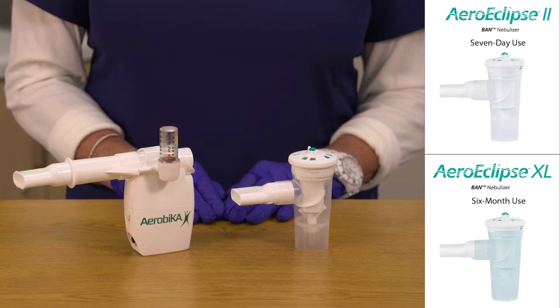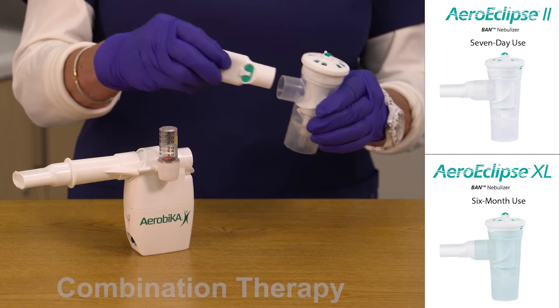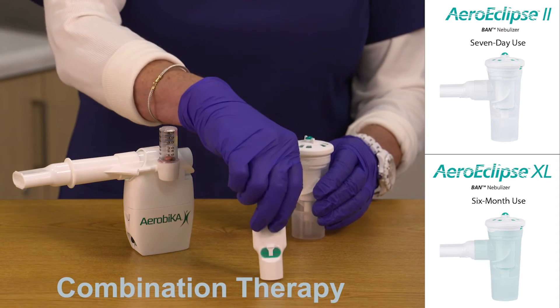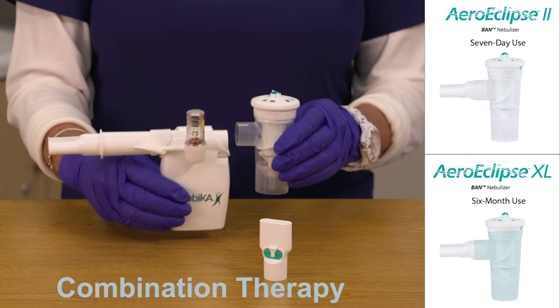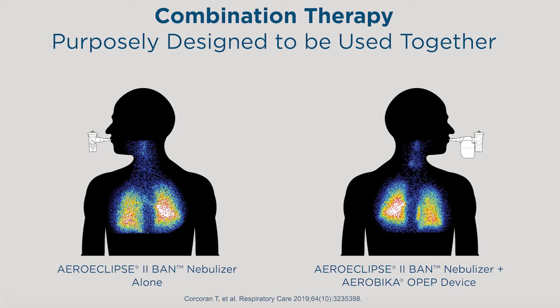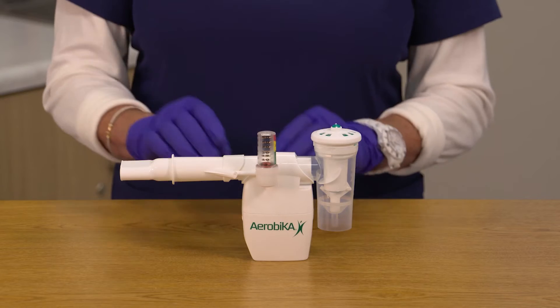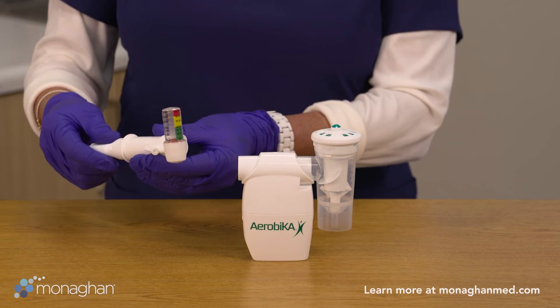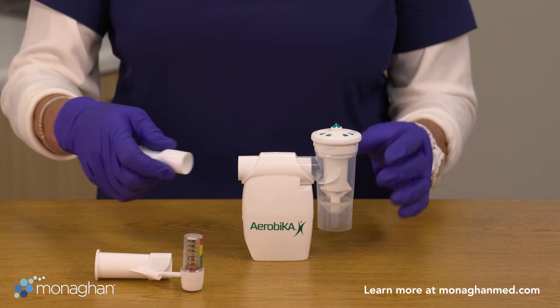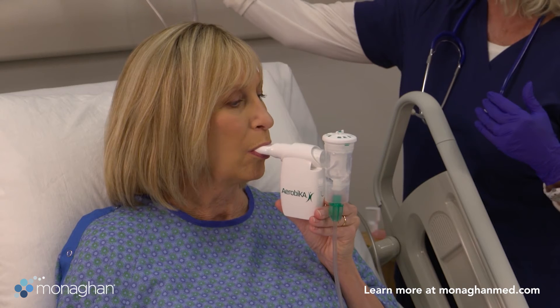The AeroEclipse BAN nebulizer can easily be added to the aerobica OPEP device for combination therapy. Simply remove the mouthpiece from the nebulizer and join it to the OPEP device. Not only does this save significant time for the caregiver and the user, but studies have shown that medication delivery is unchanged when used in combination or alone. The same efficiencies and benefits of combination use can be achieved without the use of the manometer accessory on the aerobica OPEP device as well.